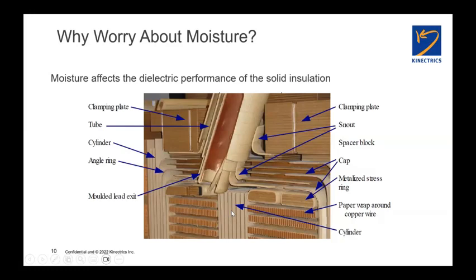We see cylinder wraps in the high-low barrier. We see static rings that are made from high density pressed board cores wrapped with paper over that. We see cap rings, angle rings, high density blocks for clamping plates, etc. So bottom line is there is a lot of insulation material inside a transformer that is cellulose. And as a rule of thumb on high voltage, large power transformers, somewhere between 3 to 5% of the weight of the transformer will be in these cellulose-based insulation materials. So it can easily reach up into the tens of thousands of pounds on a large transformer.